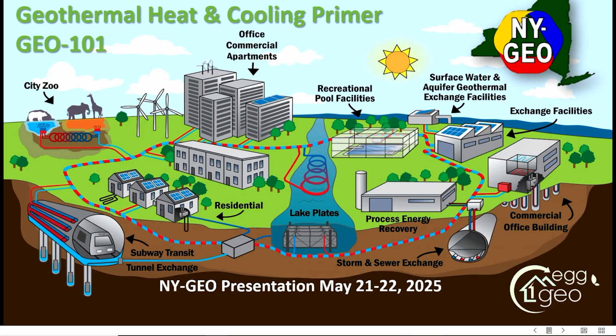This is just a pipe filled with water, and it is what is defined as the connecting circuit of a thermal energy network. Buildings within a community or a city are either cooling dominant or heating dominant, meaning in the winter you need heating, but what happens in the city, and you're going to hear more about this, some buildings like data centers and office buildings have more heat generated inside than they even need, so they need to exhaust heat. So the thermal energy network concept that you're going to hear about, and we're starting difficult, but we're going to go very easy very quickly, is that cooling dominant spaces reject heat all winter, even on the coldest day.